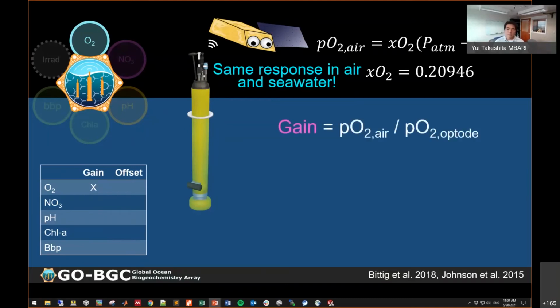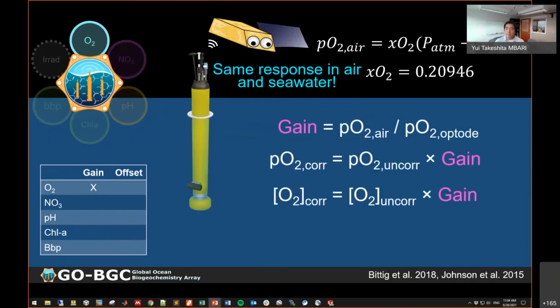And the gain is simply the ratio of this calculated partial pressure of oxygen divided by the sensor reading in the air. So, very straightforward. And we can apply this gain in either PO2 or the constant oxygen concentration domain to adjust the data. And another benefit of these air calibrations is that you get a measurement every profile, so we can assess for sensor drift over the life of the float.